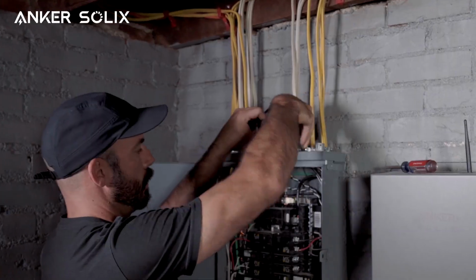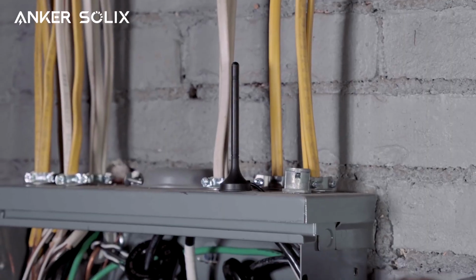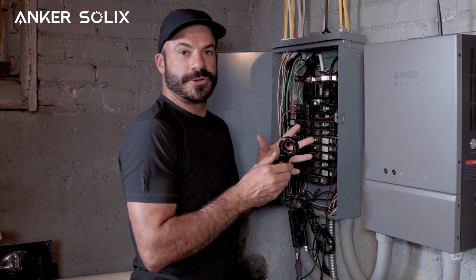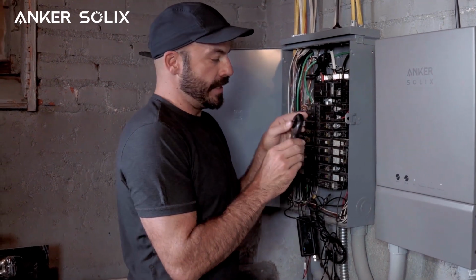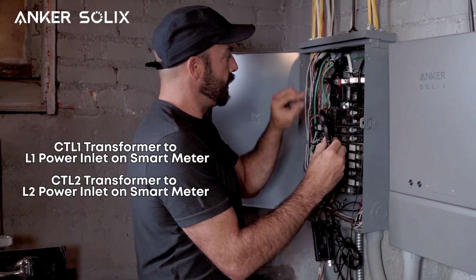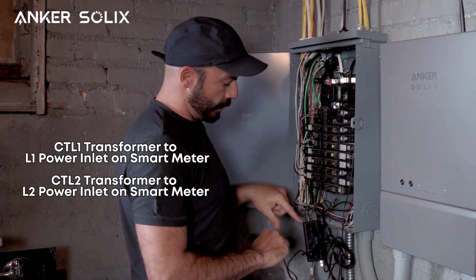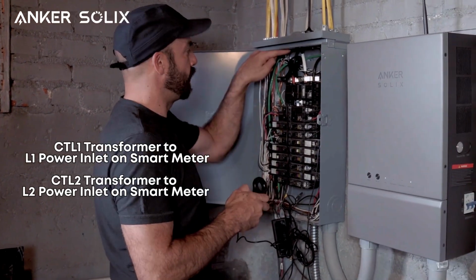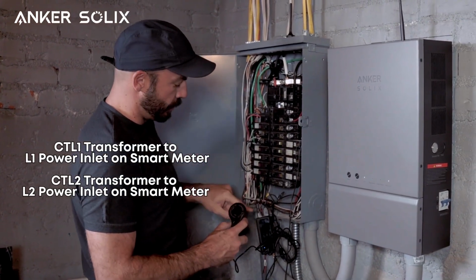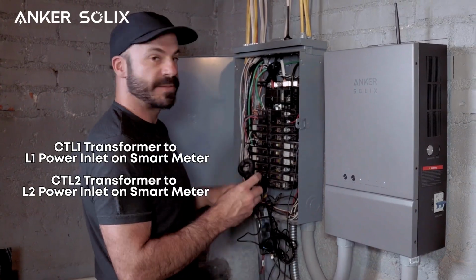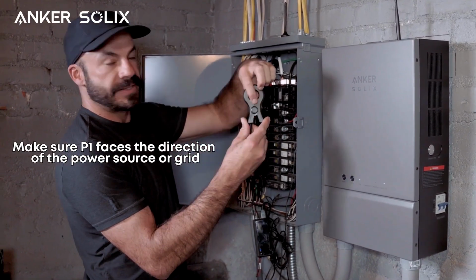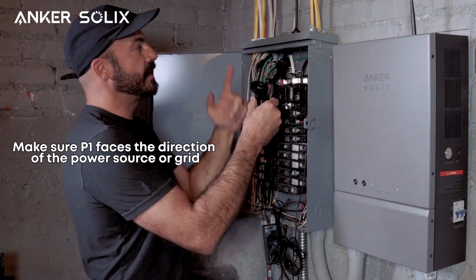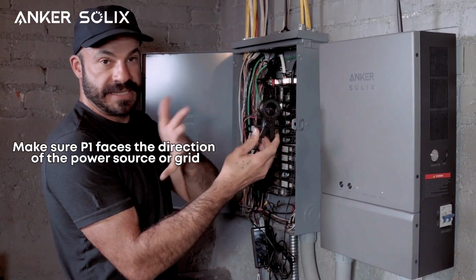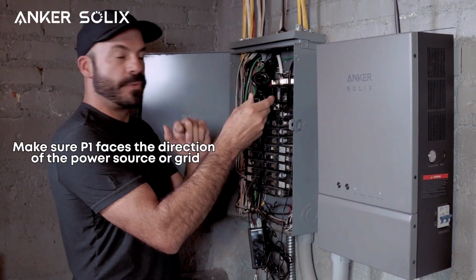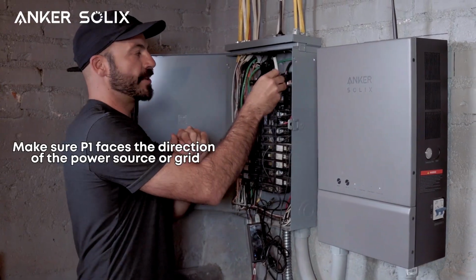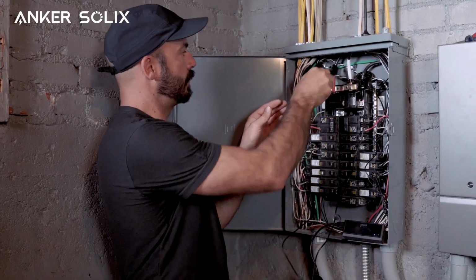Now that we've made those connections, let's install the antenna and the current transformers. When installing the current transformers, it's important to make sure the CT-L1 corresponds to the L1 power going into the smart meter, and the L2 corresponds to the L2 line. You also want to make sure the P1 marking faces the direction of your power source, which in our case is the grid, so I'll have it facing away from the array of breakers in the box. We'll do the same for the other side.